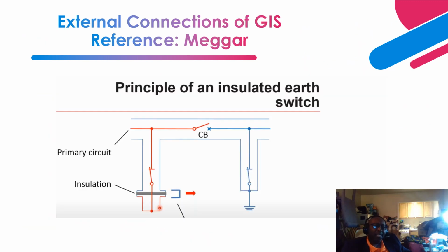So PD, partial discharge testing, is done to make sure that you don't have PD activity anywhere. And even if it is present, there are ways and means where they perform localization to identify the exact area that the PD activity is taking place. So now let's take a look at how the testing is done.